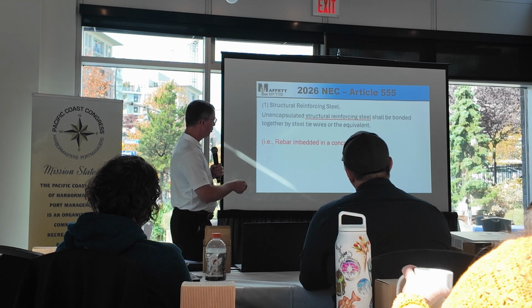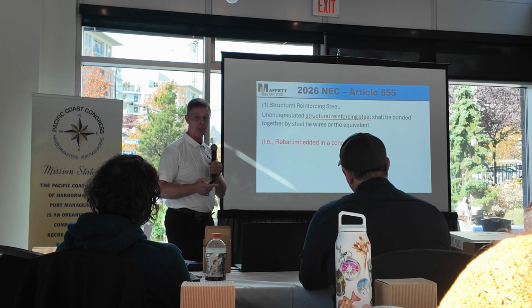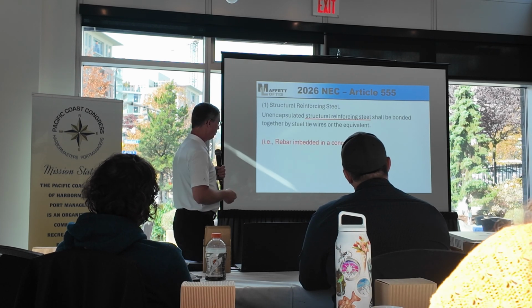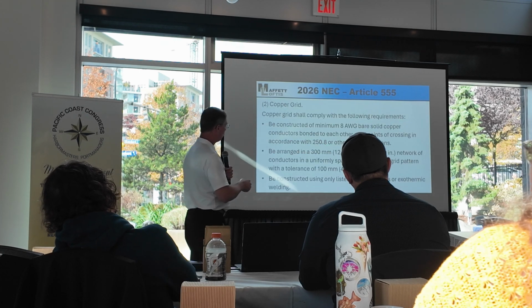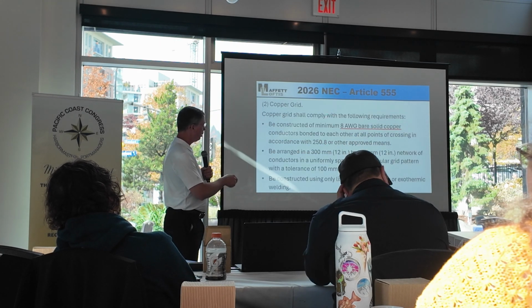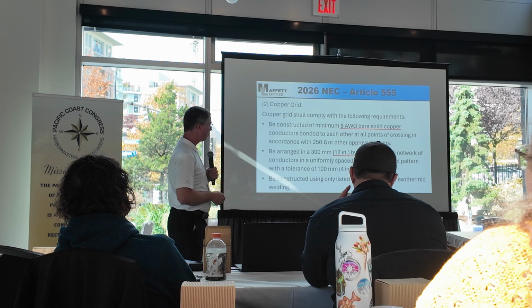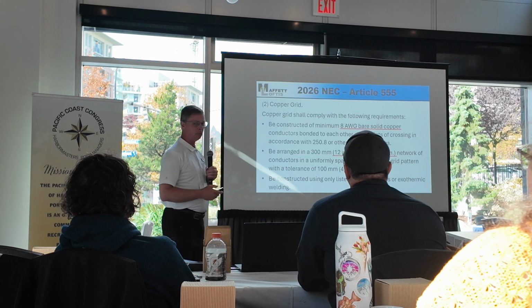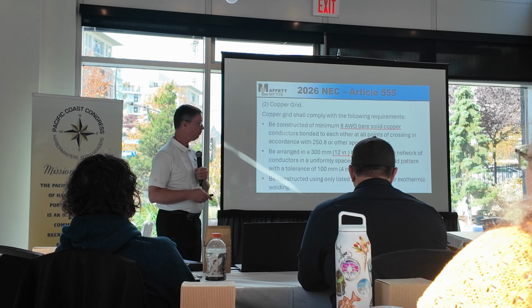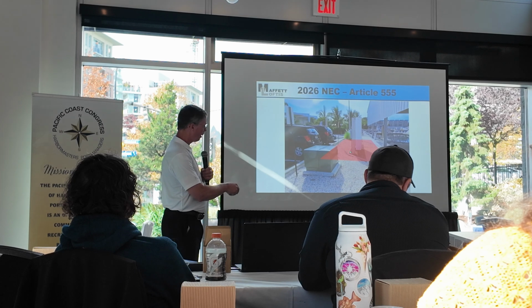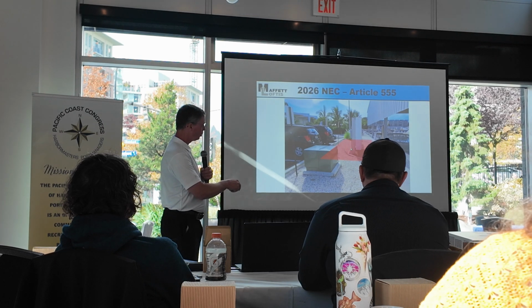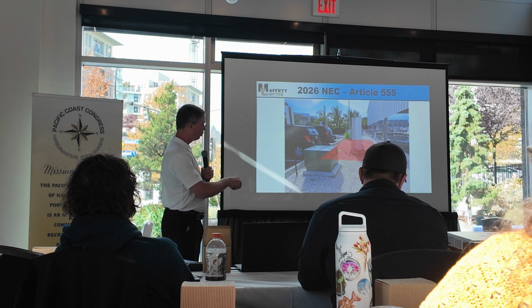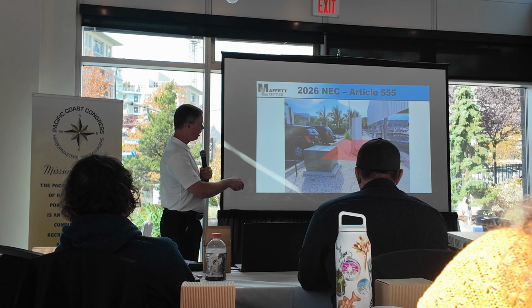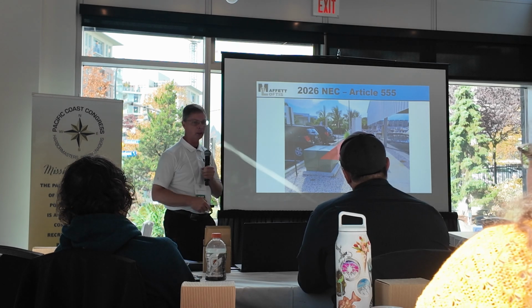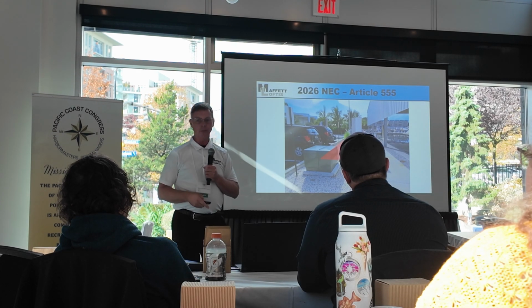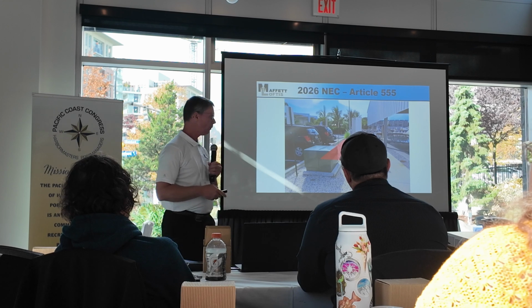You can have structural steel reinforcement in the concrete, rebar basically, embedded in the slab. But also in the gravel, you can do a copper grid with number 8 solid copper on 12-inch centers, 12 by 12, and that would be out in this space here. So you have to bond that number 8 copper 12-inch grid with the embedded concrete, and then bond it back up to the grounding bus, so that you're standing on surfaces that are bonded.